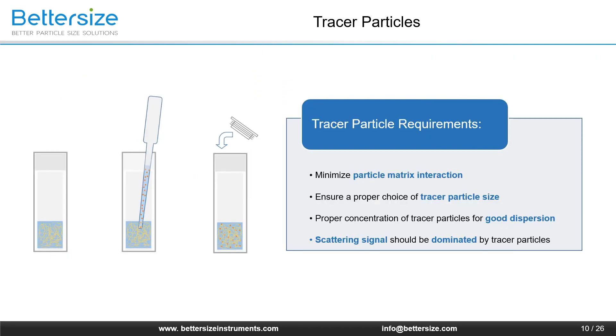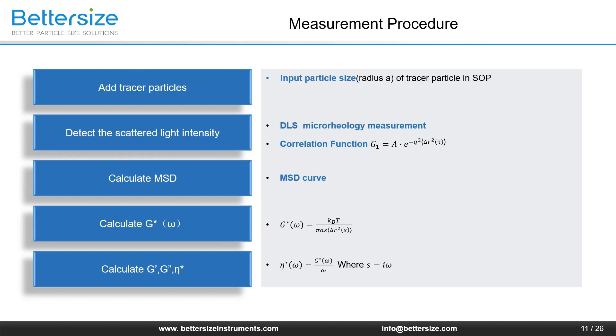When performing DLS microrheology measurements, the choice of tracer particles is very important. A key requirement is to minimize particle-matrix interactions, since any significant physical or chemical interaction between embedded tracer particles and their surroundings may alter the local environment and affect diffusivity. The tracer size used can have a significant effect on extraction of rheological parameters, and appropriate tracer concentration must be considered for good dispersion so that the scattered signal is dominated by the tracer particles. For the B-nano series, the first step is to input the particle size of the tracer particle; the instrument then measures scattered light intensity to obtain the correlation function and MSD curve, from which rheological information such as G-star, G-prime, G-double-prime, and Eta-star can be extracted.